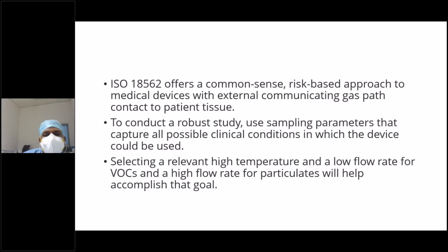And the parameters which are tested should be carefully selected. A clinically relevant high temperature should be used, and the lowest possible flows should be used for testing volatile organic compounds, and the highest possible flow rates should be used for particulate matter to accomplish the goal.